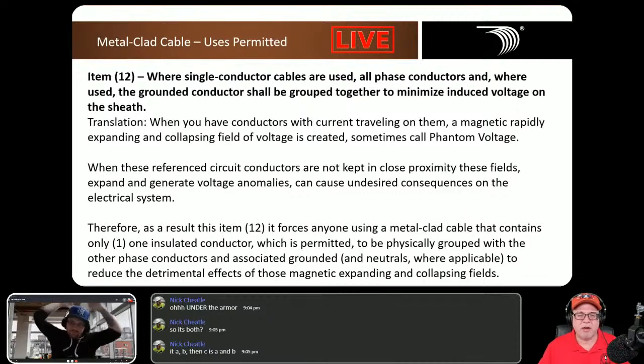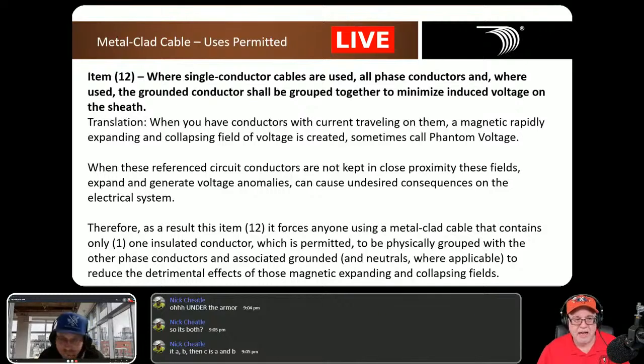Lastly, item 12 in our list is where single conductor cables are used. It says all phase conductors, and where used, the grounded conductor shall be grouped together to minimize induced voltage on the sheathing. So think of it this way, Jay, and here's how I like to explain this to people. Think of MI cable. MI cable, mineral insulated, is actually an individual conductor. And so if you need multiple conductors to complete a circuit, they're each going to be run independently.